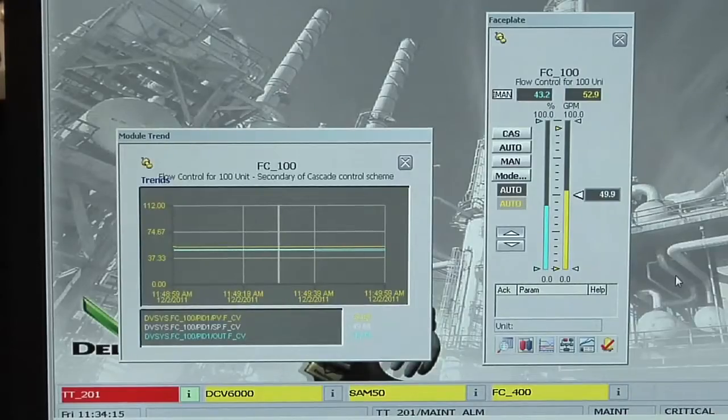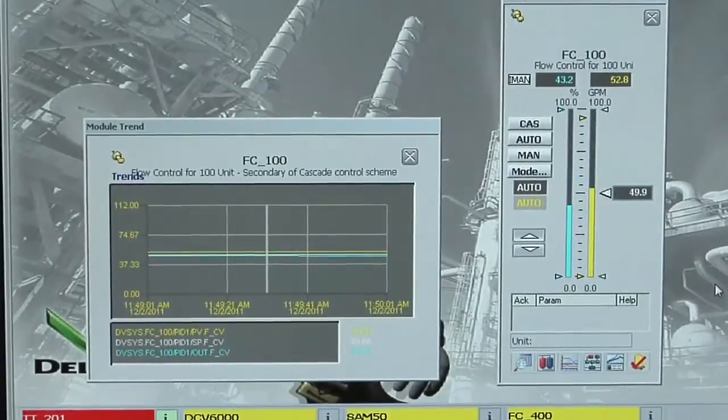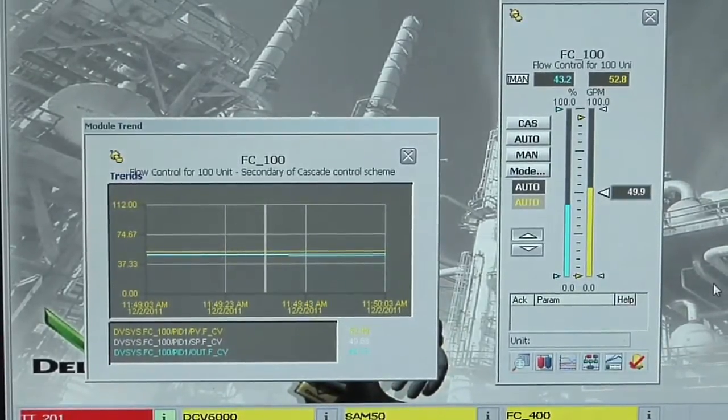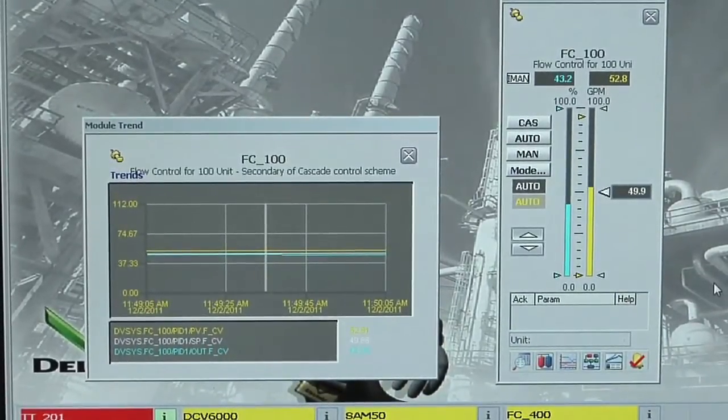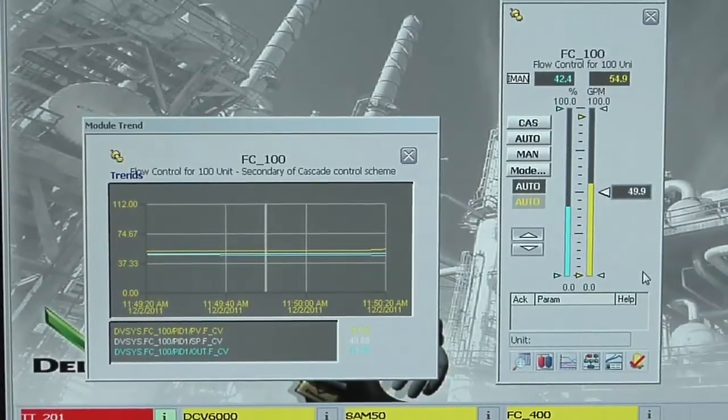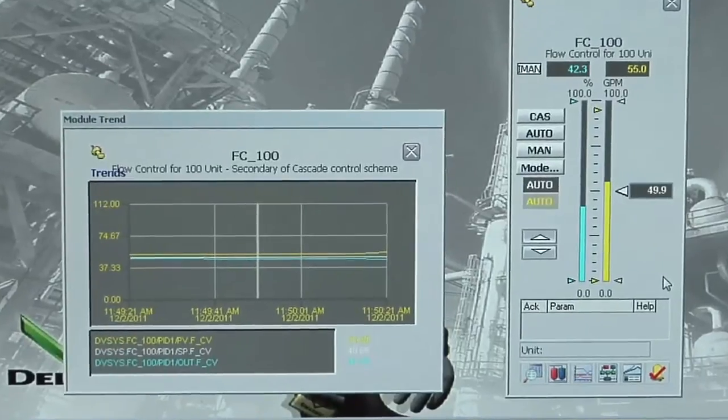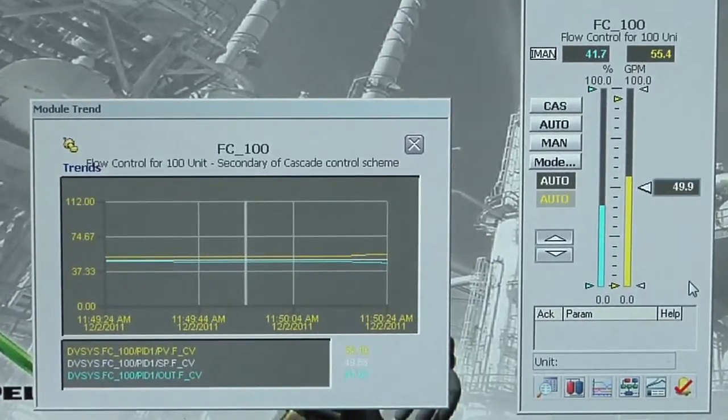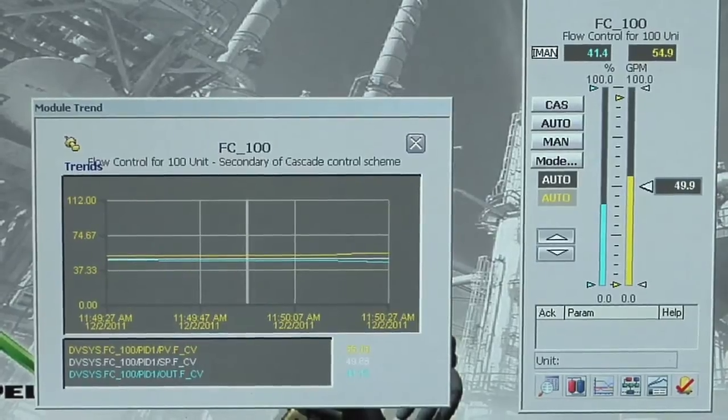Okay, so now let's demonstrate briefly what happens when we lose our process signal. So here's the controller with the process value on the right side with the yellow bar graph and the valve output with this blue bar graph. So we're holding, we're in automatic. Everybody's happy. Things are controlling well. And what I'm going to do, number one, go down to the diagnostic page.